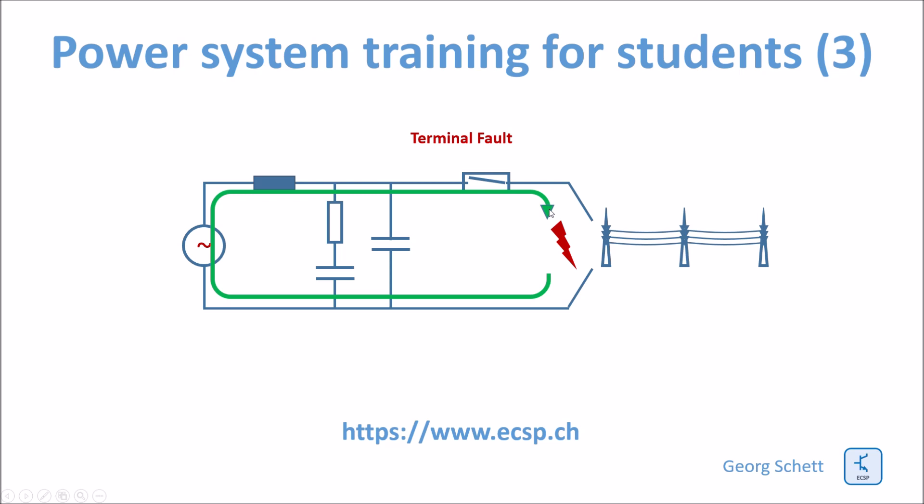It can reach up to 80 kA. In substations, there are relays. These relays are permanently measuring the current. As soon as the current is higher than normal, the relay sends a trip to the breaker. The breaker opens the contacts and interrupts the current.